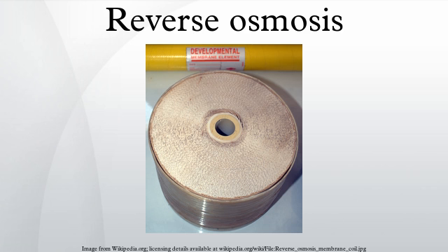The Ashqelon seawater reverse osmosis desalination plant in Israel is the largest in the world. The project was developed as a build-operate-transfer by a consortium of 3 international companies, Veolia Water, IDE Technologies, and Elran. The typical single-pass seawater reverse osmosis system consists of intake, pretreatment, high-pressure pump, membrane assembly, energy recovery, remineralization and pH adjustment, disinfection, alarm control panel, pretreatment. Pretreatment is important when working with reverse osmosis and nanofiltration membranes due to the nature of their spiral wound design.